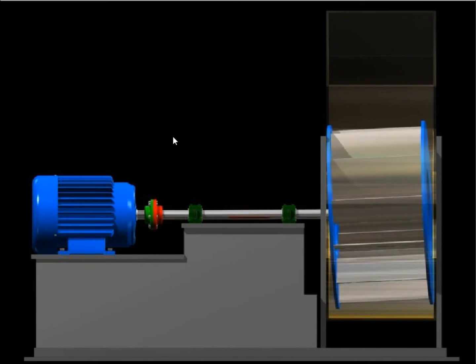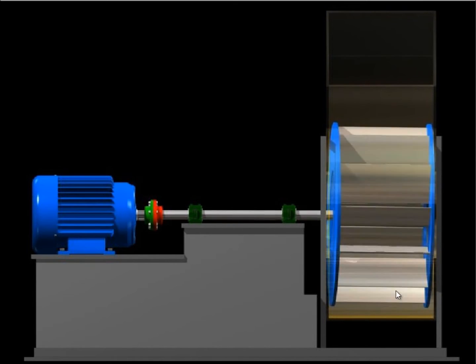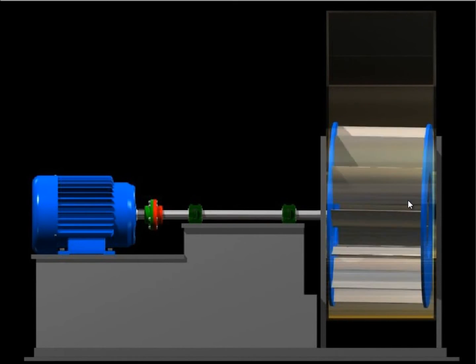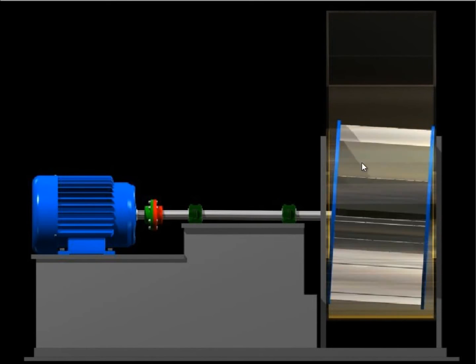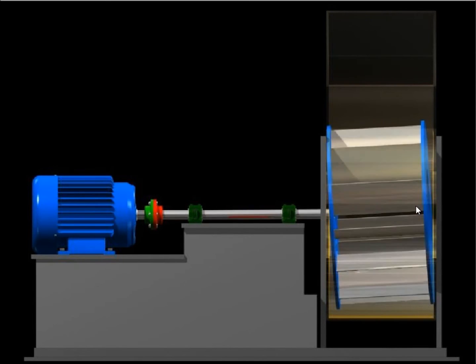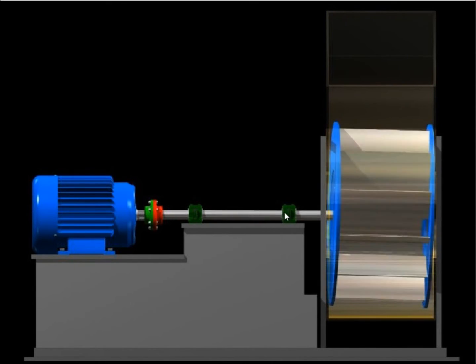So the difference is we expect to see the high vertical and horizontal vibration and high axial. So if we place sensors in this direction, we will measure that axial vibration and we would see these two bearings moving in phase with each other.